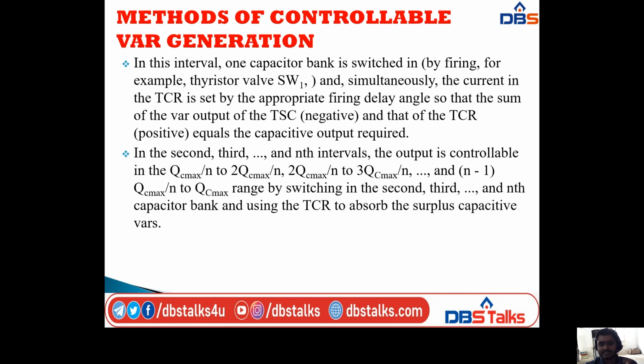Next, in the second, third, and so on up to the nth interval, the output is controllable in the range of QC maximum by n to 2 QC maximum by n, then 2 QC maximum by n to 3 QC maximum by n, and so on, up to n minus 1 times QC maximum by n to QC maximum, by switching in the second, third, and so on, nth capacitor bank, and using the TCR to absorb the surplus capacitor VARs.